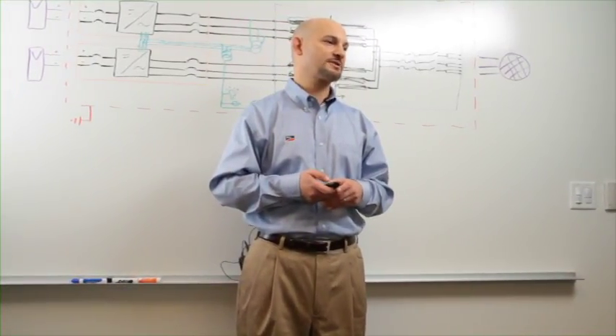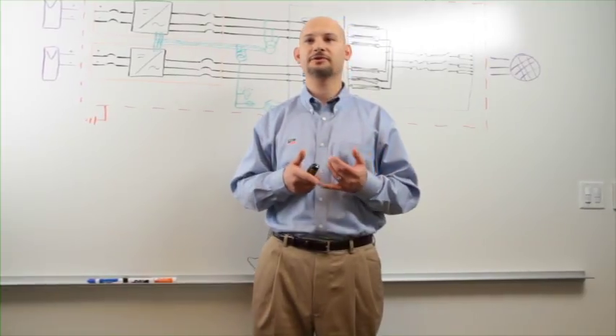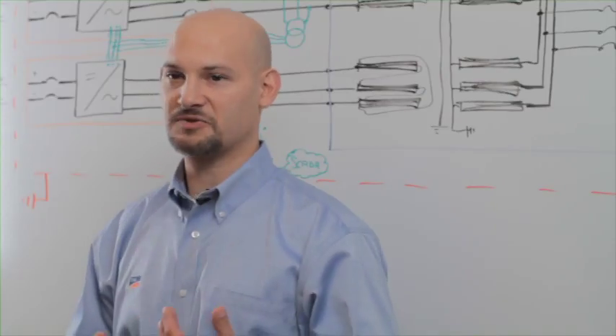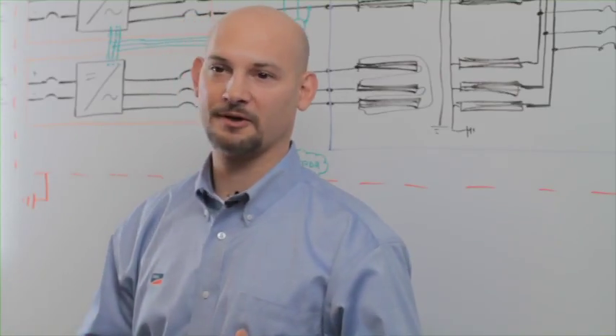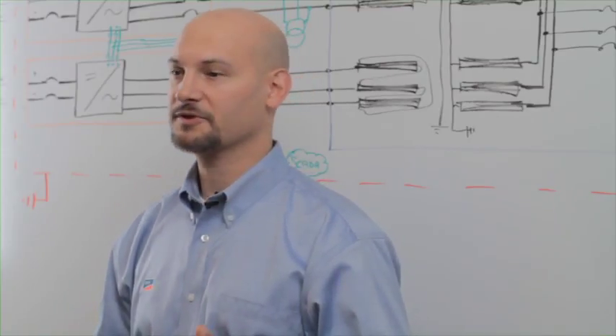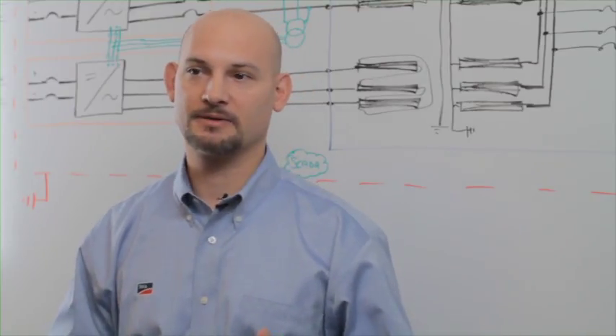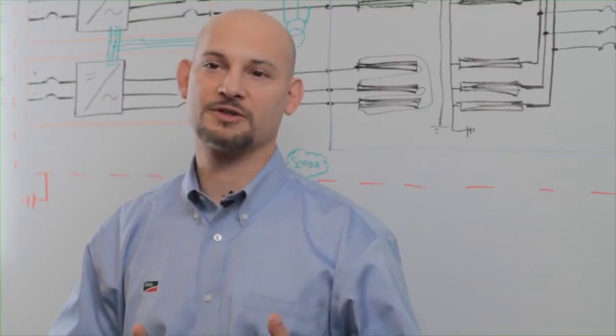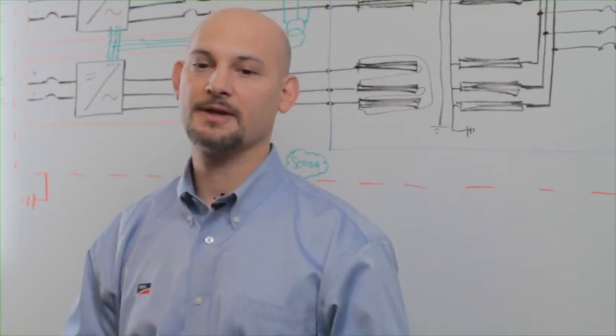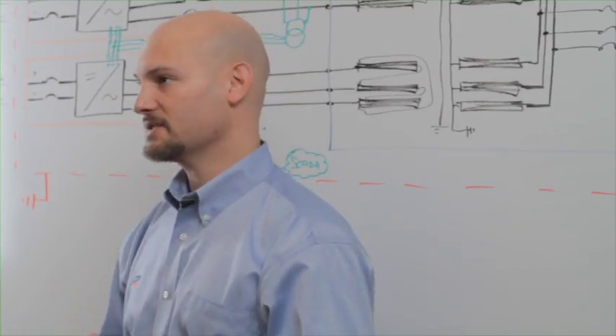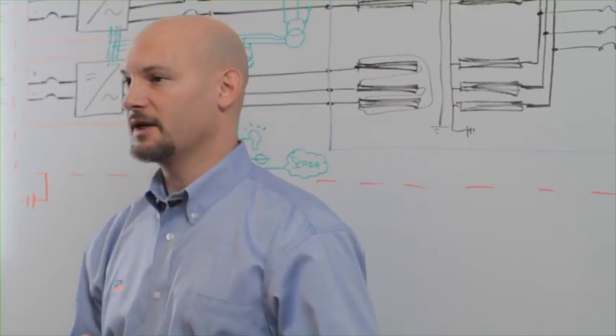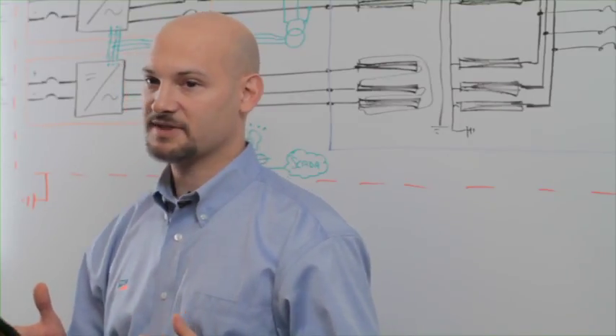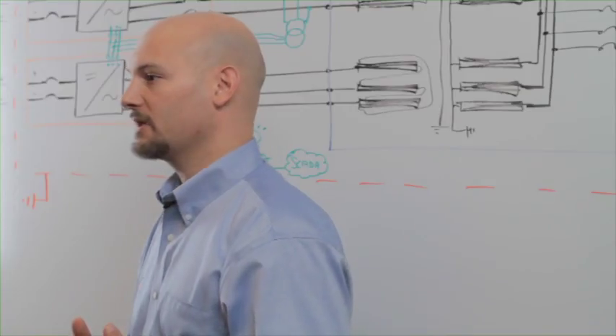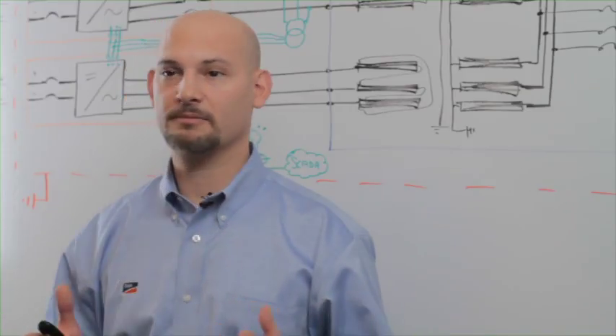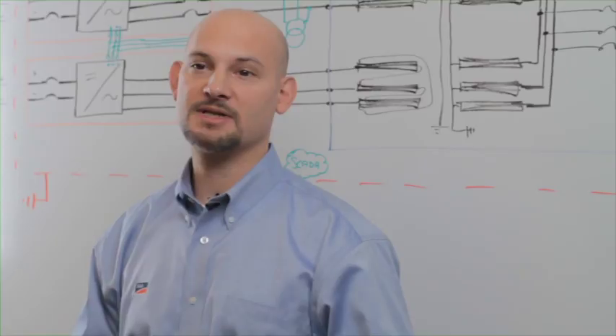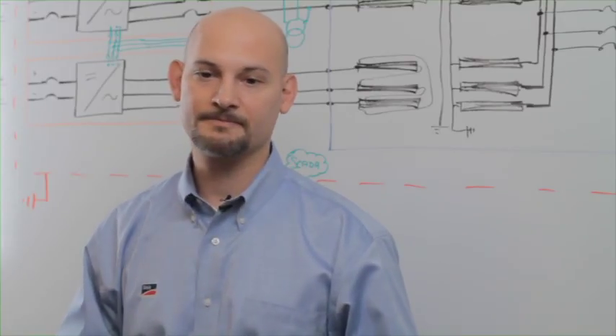The configurable options include the interconnection voltage, of course. We have many utilities in North America, each with their own distribution voltages, and we're able to provide the medium voltage transformer to tie into any of those voltages. The DC disconnecting means could be an integrated SMA disconnect right on the skid, or it could be an integrated circuit breaker panel board with zone monitoring CTs, all tied into your SCADA system.